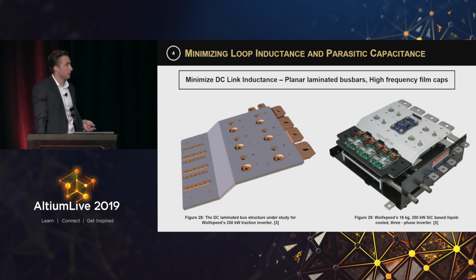The big thing is the loop area needs to be minimized. The DC link connections should be planar laminated bus bars or PCBs that are sandwiched together. Ideally, you should use high-frequency film capacitors with low equivalent series inductance, located as close to the pins of the power terminal as possible. If you really want to optimize this, you can use a multi-physics program such as COMSOL to analyze the high-frequency current paths and maximize magnetic field cancellation.